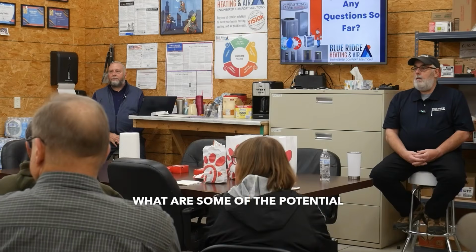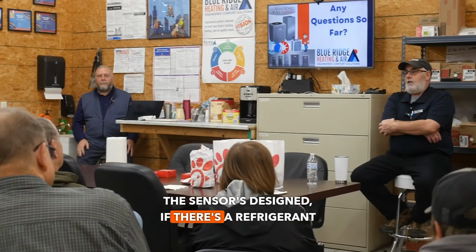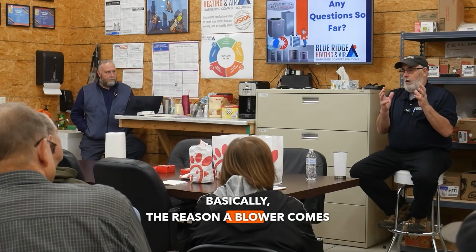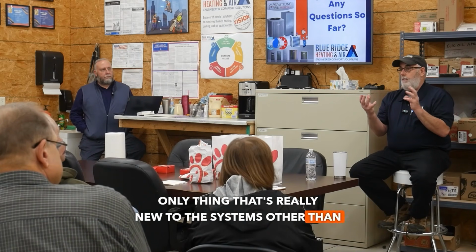Right. So, sir, you had a question? What are some of the potential kinks that it spoke of? I think the sensor. The sensor is designed so that if there's a refrigerant leak, the compressor shuts off outside and a blower comes on. Basically, the reason the blower comes on is to dissipate that volume of refrigerant in the system. And basically that's the only thing that's really new to the systems other than the conventional systems that we have today. So I know for our refrigerant leak detectors, we trust them, but they're a meter.